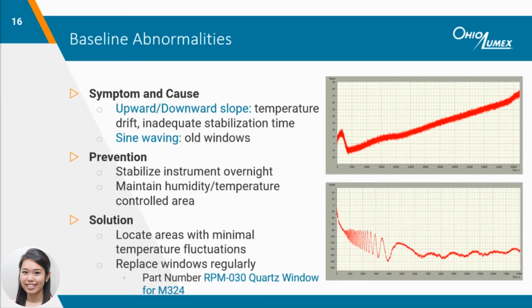The M324 is very sensitive to temperature and humidity, so baseline drift can also occur if the instrument is near an air vent and the AC kicks on, or if the trailer door is left open for a few minutes. Ideally, the M324 should be set up in a humidity and temperature controlled room to prevent it from drifting out of calibration, especially during analysis. Sine waving can also occur during the initial warm-up period and is an indicator that the windows are old if the baseline doesn't settle out.